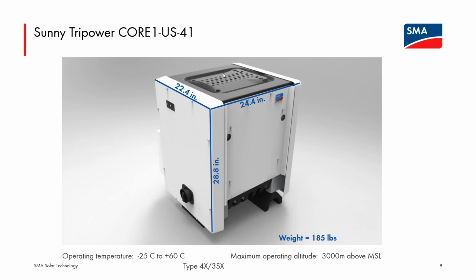You can see a little better in this image the holes, the perforations in the top of the inverter, and can see kind of the ribs of that fan tray at the bottom, a little bit on the dimensions and weight of the inverters. And again, all of the power classes are the same. The operating temperature goes down to -25 C, but the inverter can be exposed safely down to -40 C. If the inverter does wake up and it has not achieved -25 C, there's a very specific error code waiting for minimum operating temperature that it will display until it reaches -25 C and goes into production.